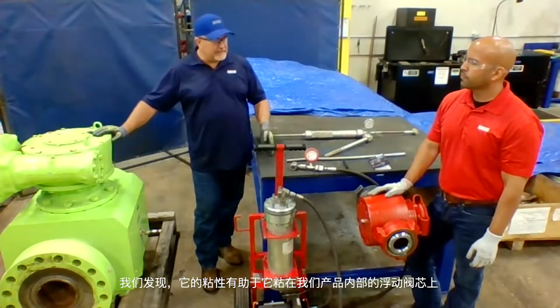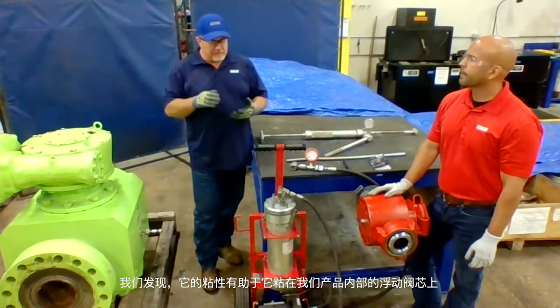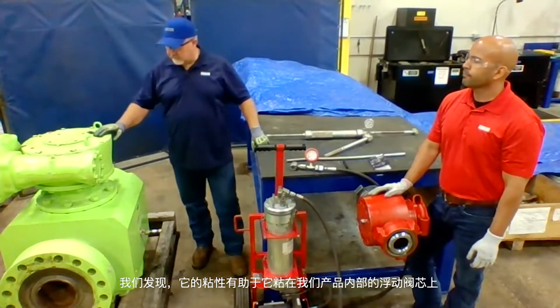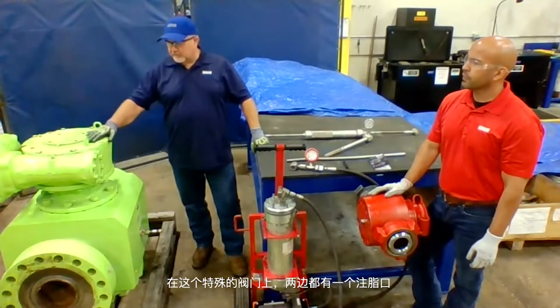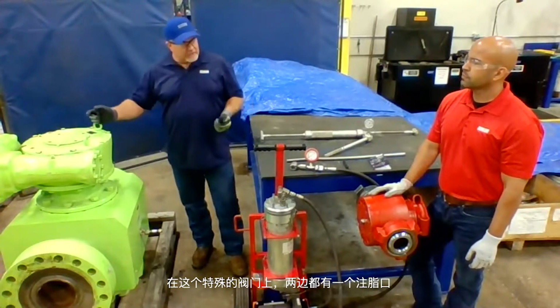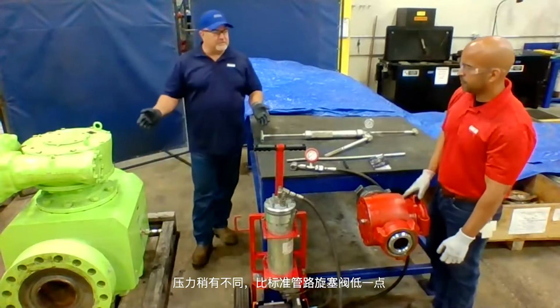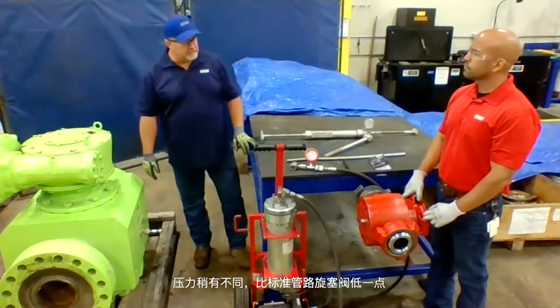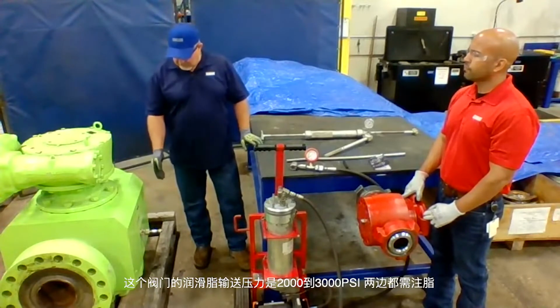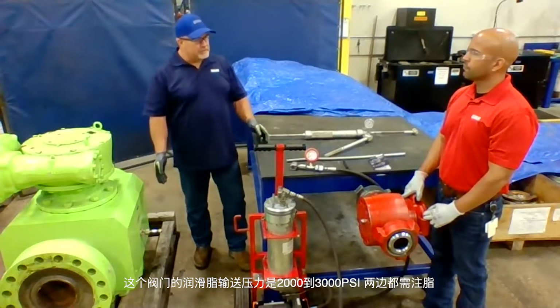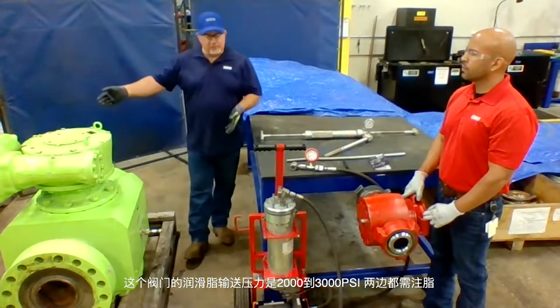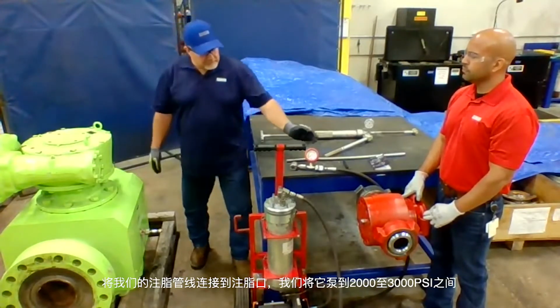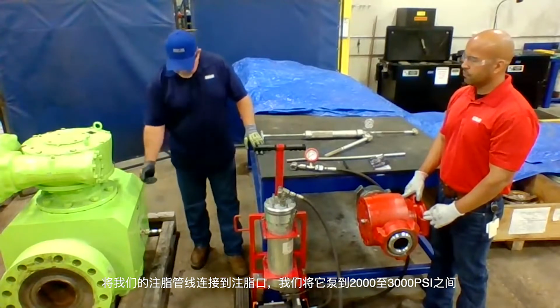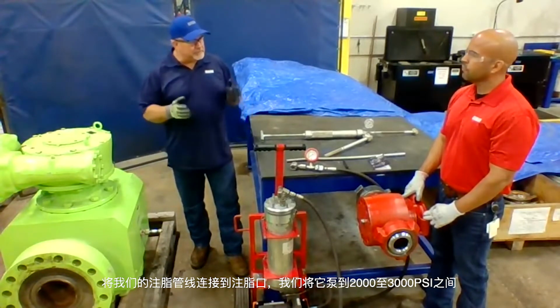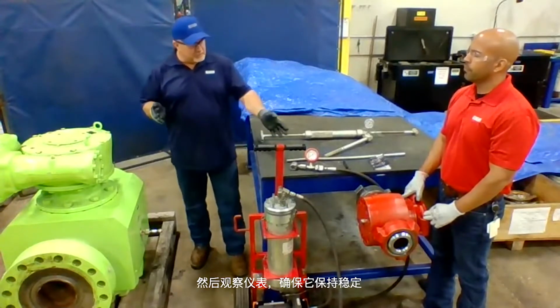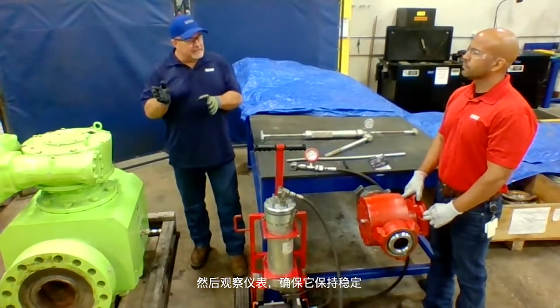We find that the tack helps it stick to the products inside of our floating plug design. On this particular valve, it's got a grease fitting on both sides. The pressure's slightly different. It's a little bit lower than the standard line plug valve. The delivery pressure on grease for this valve is 2,000 to 3,000 pounds, and you do both sides. So we would take our line and hook it up to the grease fitting, pump it up to somewhere between 2,000 and 3,000 pounds, and watch the gauge to make sure that it stayed steady.